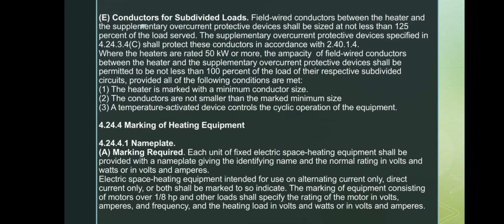Next slide, we discuss conductor sizing for subdivided loads. When heaters are divided into smaller circuits, the wires that connect the heaters to the supplementary overcurrent protective device must be sized at least 125% of the load. However, for heaters 50 kilowatts and above, the conductors may be sized at 100% of the load if three conditions are met. First, the heater must be marked with a minimum conductor size. Second, the installed conductors must not be smaller than that marked size. Third, the heater must use a temperature-activated device that controls its cycling.